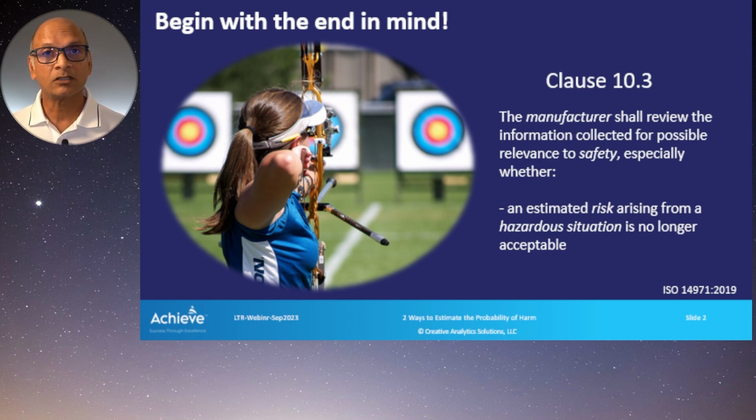and a good estimation of the risk overall, because we want to be able to compare the change in the post-market phase to our estimated level to see if that estimated level still is acceptable or not. Why? We need to take action. If it is no longer acceptable, we need to take quick action. And if our methodology for estimation of risk is not practical enough and not directly linked to our post-market information, we find that a little bit challenging, right?